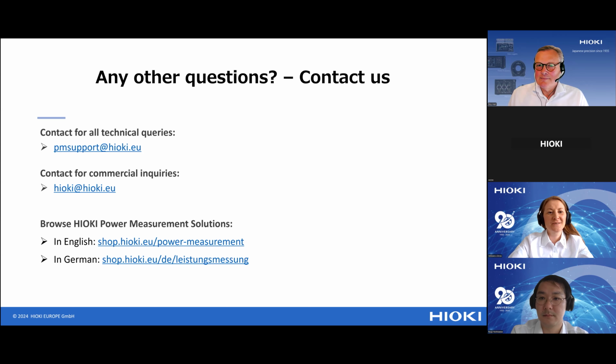It's an interesting question. Sorry, does it mean synchronize with the PW6001 and 8001 by optical link? Yes. Unfortunately, it's not possible. Only the same instrument can synchronize by optical. The same goes for the BNC. It's not possible to synchronize a PW8001 with a PW6001.